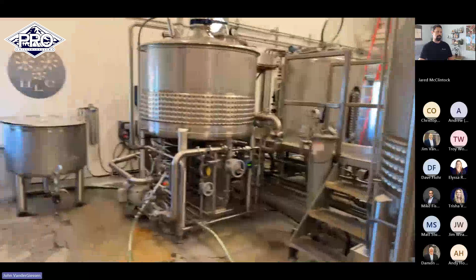The cooling is done with a tank of ice water. That represents one of our large cooling loads, where every day that we're brewing, we need one of these tanks full of ice water produced by the chiller. Simultaneously on those days, there's a lot of wash down and actually hot water used to produce that barley tea itself that's in the product. So the cooling and heating are usually occurring at the same time, which is why we're particularly interested in a CO₂ chiller system that can potentially do both at once to utilize what would be a waste product.